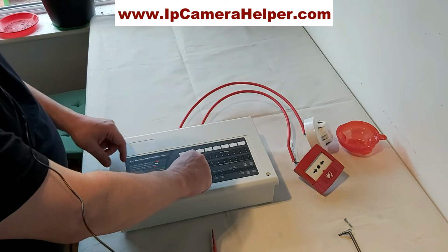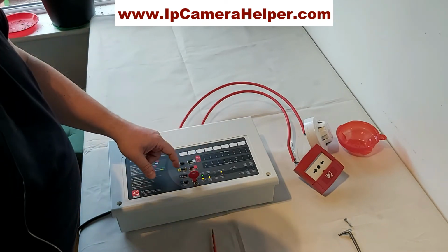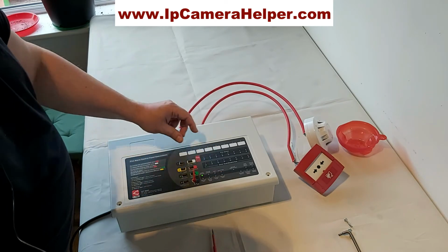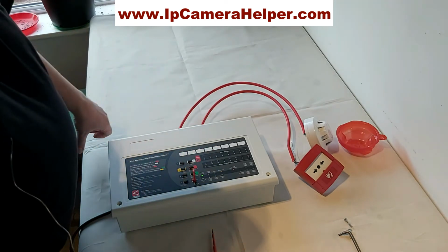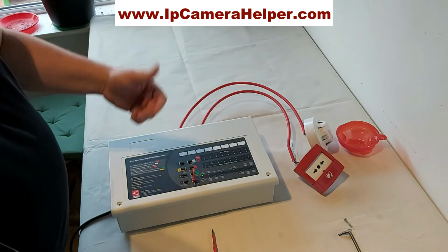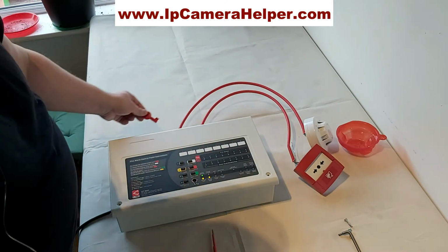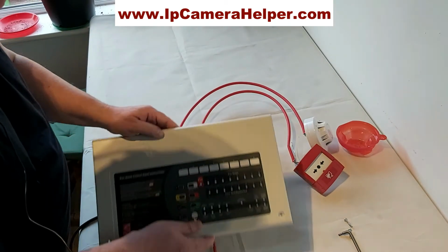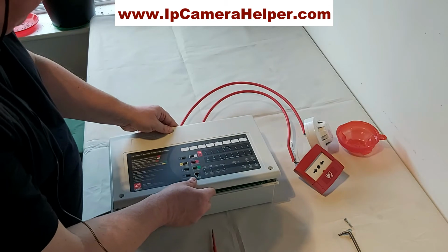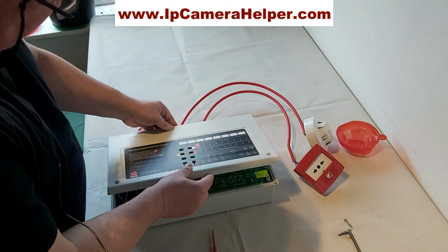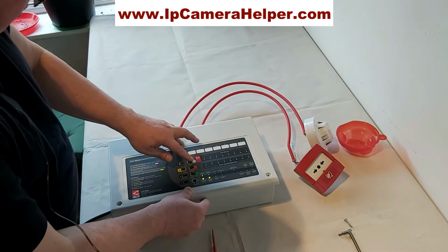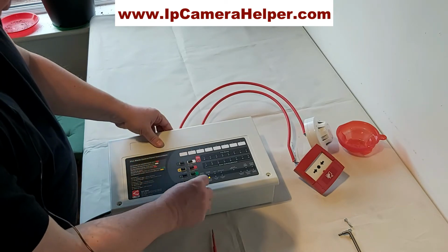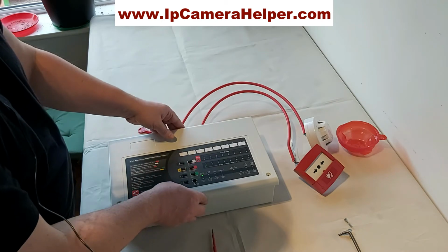Now there's no point in resetting them, because even if you reset it and I don't fix the fault, for a moment it will disappear, and it's back. So there's no point in resetting if you didn't fix the problem. You can silence. Oh, again, it's beeping. There's that single beep. And we can press silence internal sounders, and it's still flashing here. It's not beeping anymore.